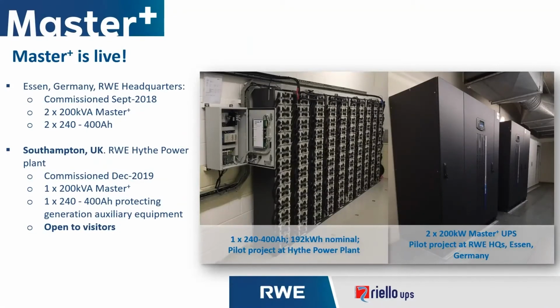The Master Plus solution is not just a concept, this is a live and operational system. There are two pilot projects running. The first was commissioned in September 2018 at the RWE headquarters in Germany. This comprises two 200 kVA UPSs. The second is in Southampton at the RWE Hythe power plant, which was commissioned in December 2019, and this system comprises a 200 kVA UPS. These can be seen in the images on the right hand side.